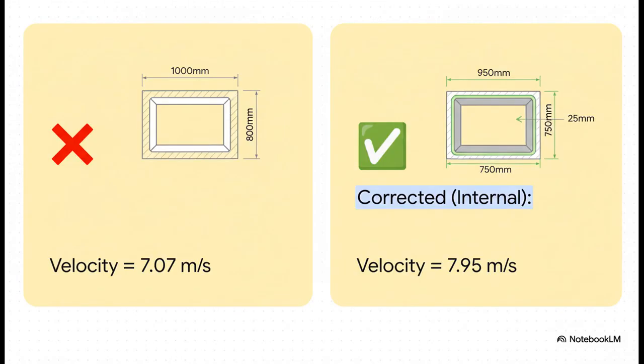Let's look at the numbers. Your initial math might say you need a duct that's 1,000 by 800 millimeters on the outside. You run the calculation, and it gives you an air velocity of around 7 meters per second. Looks good, right? You're within the limits, but here's the catch: CLIMAVER panels are 25 millimeters thick. That means the inside space, the actual area the air has to move through, is smaller. When you redo the math with that smaller internal area, guess what? The actual velocity jumps up to almost 8 meters per second. All of a sudden, you're dangerously close to breaking your own design rules.